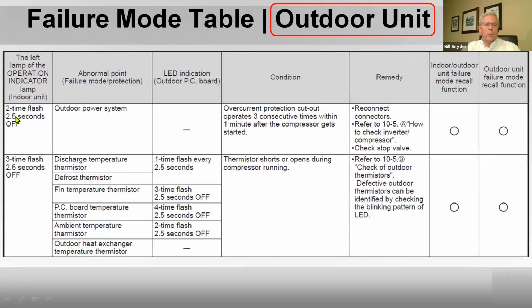Now, if I switch over here to the outdoor unit, you can look at a 2 flash on the outdoor unit, and that's saying you got an overcurrent protection. That's the, looks like amp probe, those coils that are looking at the compressor. That's what this thing is looking at. It's saying the inverter doesn't like what it's putting out, so it's going to shut down or give you a 2 flash code. Make sure you're on the right book, because these codes change from unit to unit, and between the indoor and outdoor unit they change.